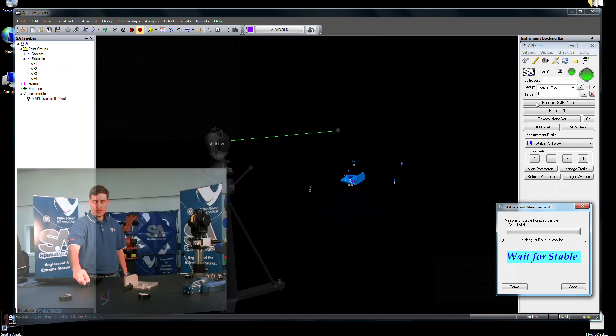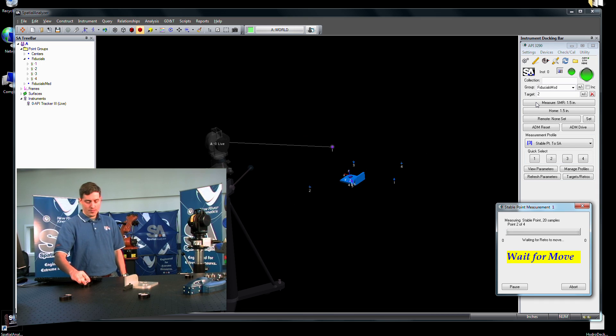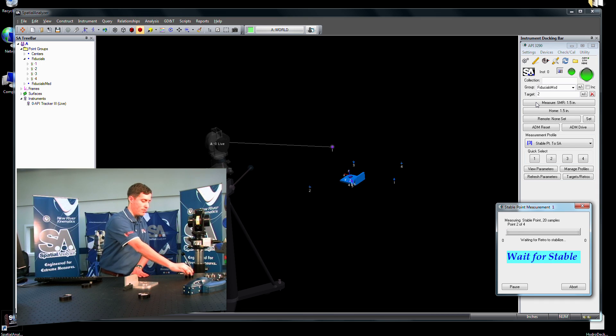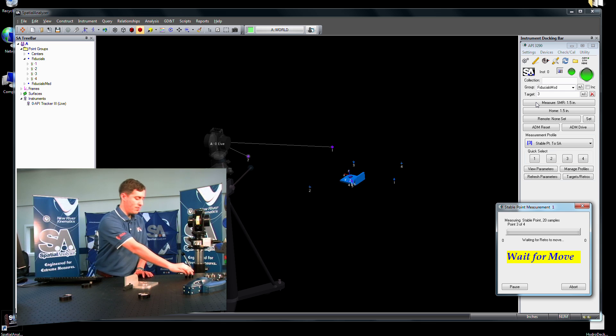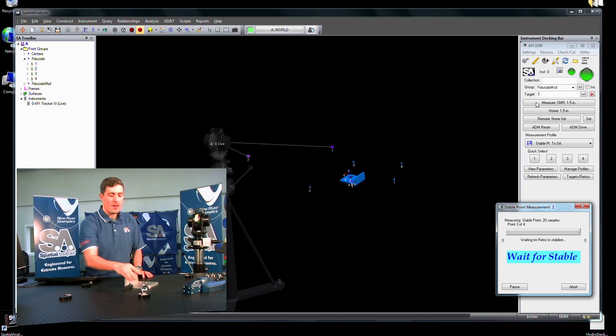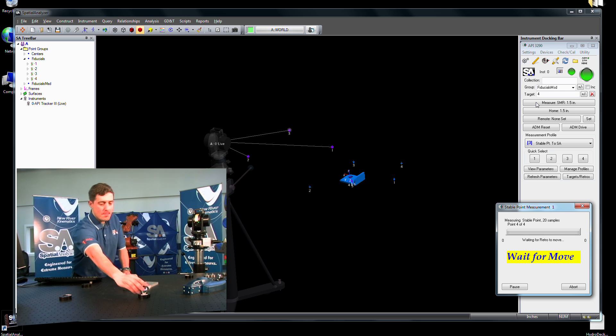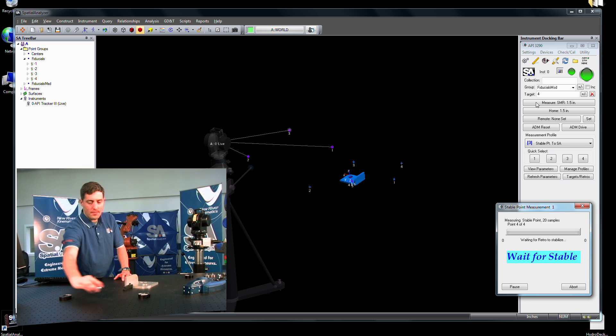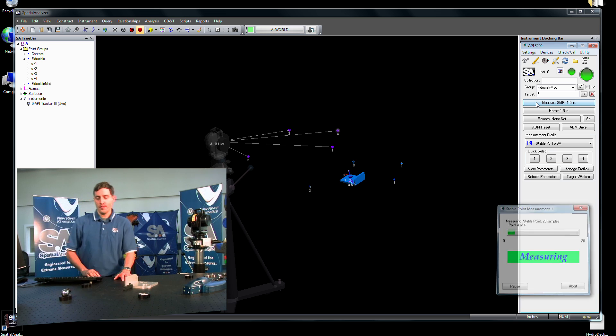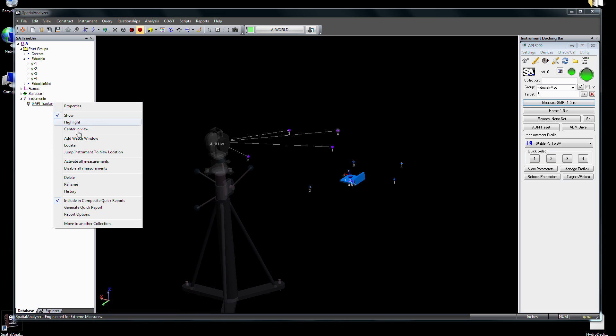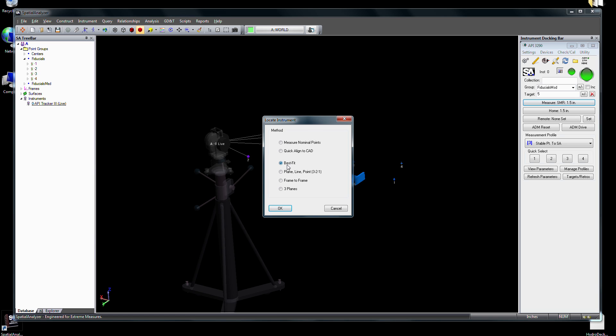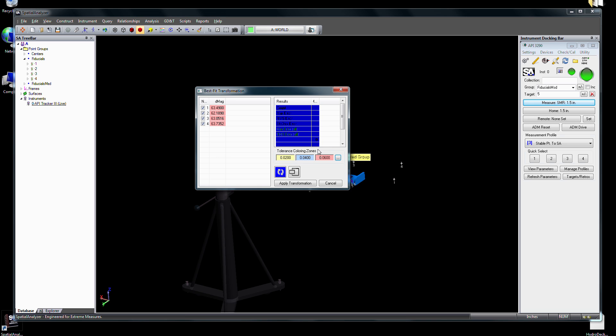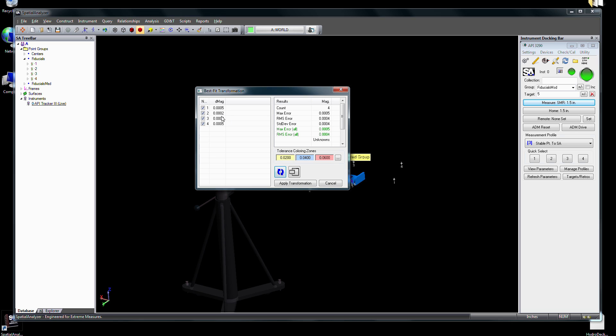If you don't have a CAD model, it's just as easy to align to a set of constructed nominal points using SA's best fit alignment capability. Simply measure the points, then indicate their nominal counterparts. With a simple command, your measured points are snapped to the nominals, and the instrument is now in place.